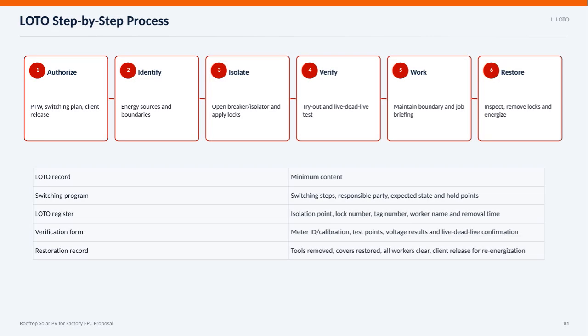Here we have the step-by-step process for lockout-tagout, or LOTO, which is critical for ensuring safety during electrical work. First, we authorize the procedure by securing proper permits to work, reviewing the switching plan, and getting client approval. Then, we identify all energy sources and establish clear boundaries to prevent accidental re-energization. Next is isolation. This means opening breakers or isolators and applying locks to physically prevent power flow. After isolation, we verify by conducting tests, including the live-dead-live test, to confirm the equipment is truly de-energized.